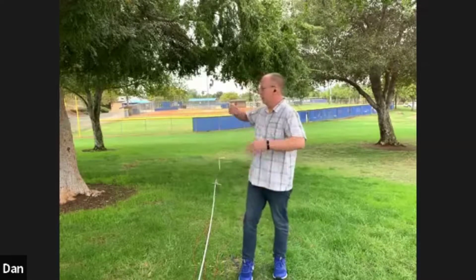Now, without doing the math on them, those sure look like we're within 5% of each other. So we'll take these numbers. What do those three numbers average out to, Idral? They average out to 77.05. 77.05 ohms between the ground rod over here and the soil that surrounds it.